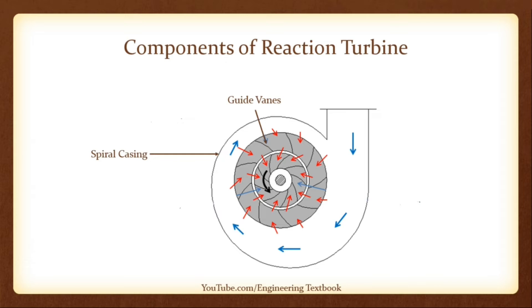Guide Vanes. This component of the reaction turbine is attached to the spiral casing. The most important function of guide vanes is to ensure that water hitting the impeller blades is directed along the turbine axis. Otherwise, the water will create a strong vortex as it passes through the volute casing, making the impeller blades inefficient to rotate. With modern turbines, the angles of these vanes are flexible. According to turbine load, the flow of water can be adjusted by changing the angle of these guide vanes.